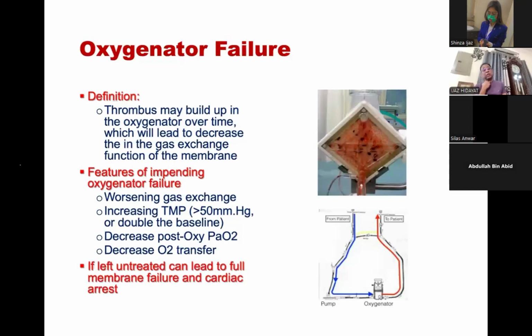a decrease in the post-oxygenator PO2, and a decrease in oxygen transfer. So number one: once you initiate the ECMO, you always do the baseline TMP. Usually you will find it depends on the oxygenator. In cardiac cases, we get a baseline of around 16 to 20 millimeters of mercury, and we recommend that if it goes to double the baseline, you can change the oxygenator by elective methods. And number two is your post-oxy. Usually the post-oxy you will get is above 450 millimeters of mercury.